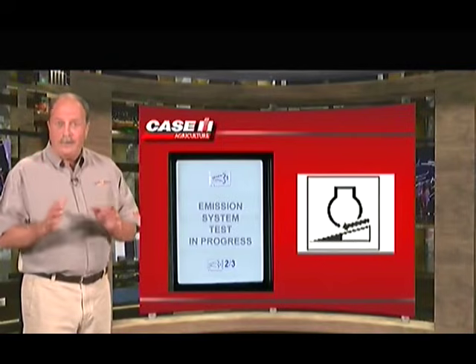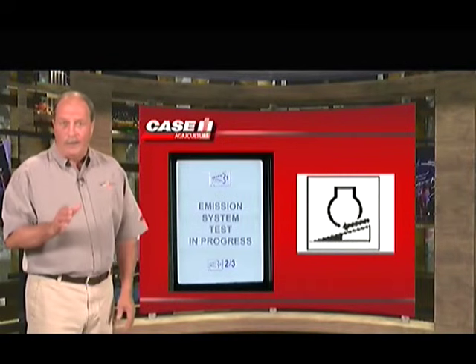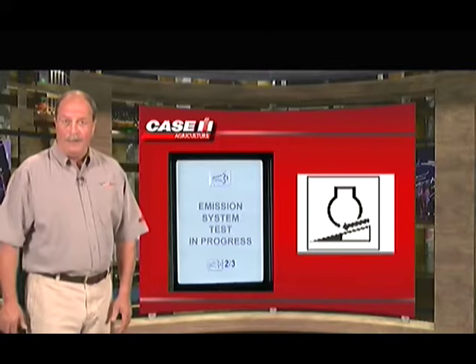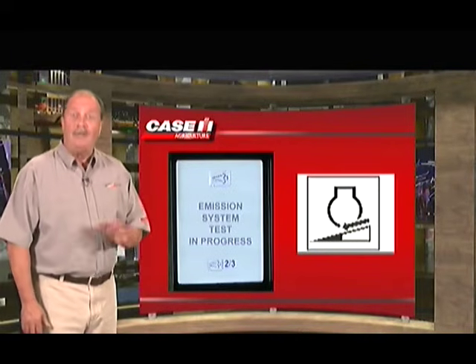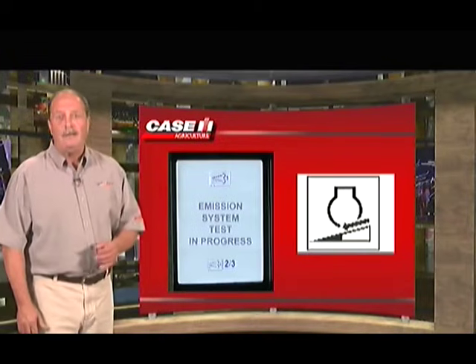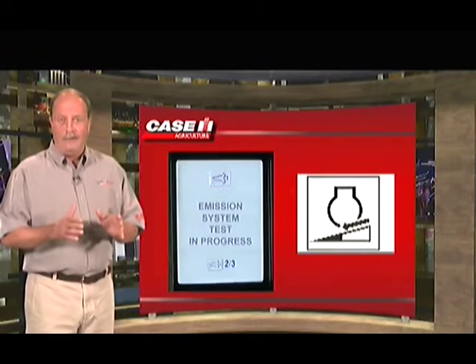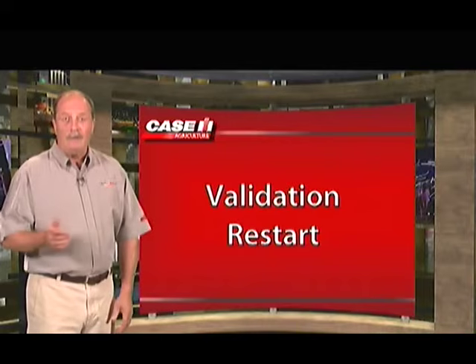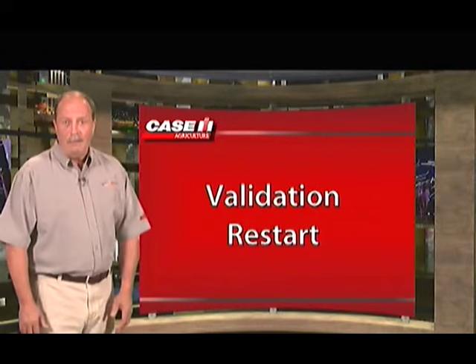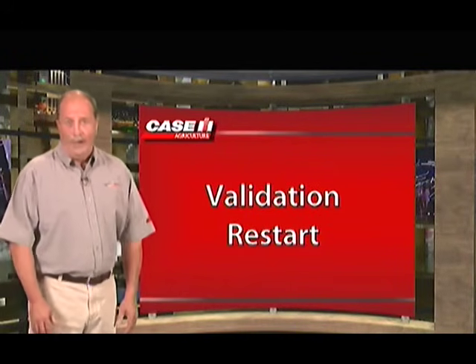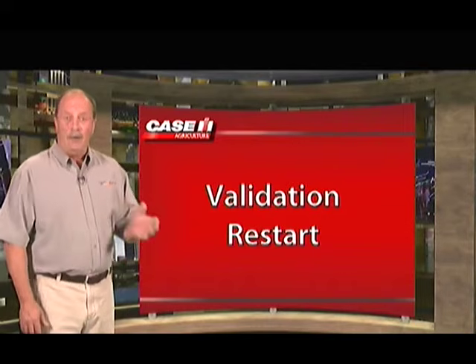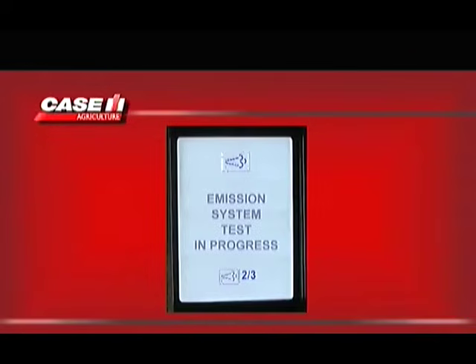If emissions system test in progress is still present and the engine derate is present again, the emissions test is not complete and the unit needs continued operation to finish the test. If the engine derate is present, use another validation restart to continue full load operation before the exhaust temperature starts to cool down. Continue operation of the unit after the restart. If the emissions test has run for 30 minutes with no results, you may have exceeded the 30-minute validation restart.